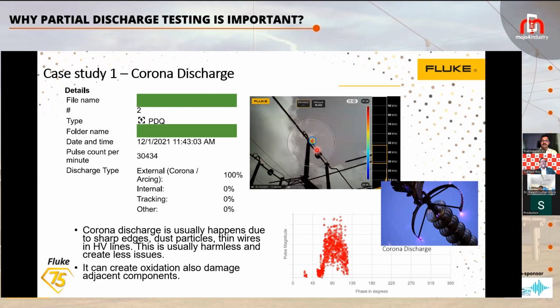And most of the people today will be aligned or knowing the partial discharge analysis through the PRPD technique, phase resolved pattern. And this is what our instrument does: from the acoustic signal, we have an algorithm built in, and also correlate the sound to the nearest or more suitable PRPD curve. And from this analysis, we are arriving at which partial discharge is happening.